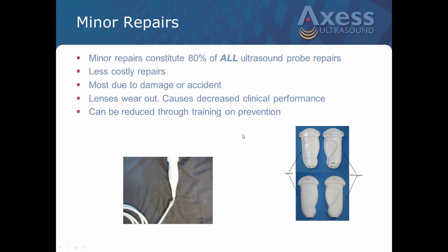Okay, again, just kind of sticking with how some of these newer probes and so on are really a different breed and a pain for all of us in trying to determine what's wrong. And I'm going to stick on the C5-1 for a minute. It's got a very unique lens on it. And again, when I talk lens, this is the membrane or lens piece that touches the patient. But Philips, in trying to keep a clean, well-defined image within heavy patients, they've got a lot of power coming out of it, as I said. So they've got a three-part lens. They've got a base silicone layer and a top silicone layer, but right in the middle is an ultra-thin layer of aluminum.